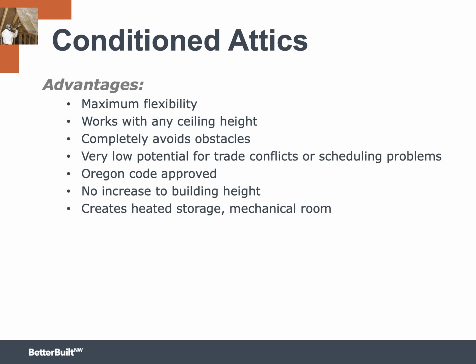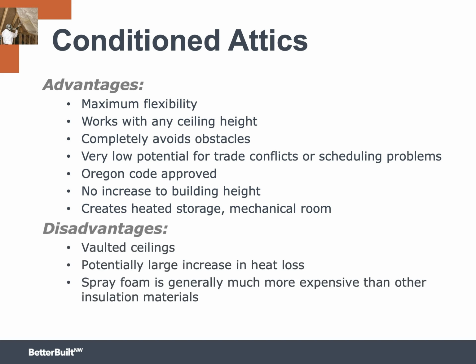Here are some advantages of conditioned attics. They give you maximum flexibility. You can get to just about any place above the ceiling. It works with any kind of ceiling height. It really avoids most of the obstacles that you might run into in terms of beams and other structural members. There's less potential for conflicts among the trades or scheduling problems. There's no code issue. There's no increase in building height. It does create extra usable space. It can be an interior utility room for your furnace and ductwork. It could also be heated storage. But there are some disadvantages too.